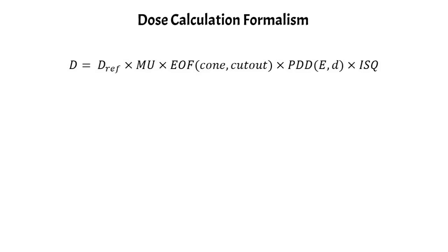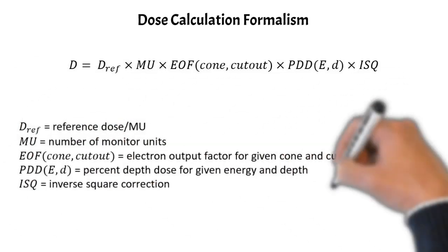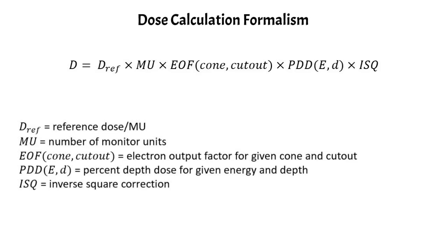This is the formalism here, and I'll write down a few of the terms. DREF is your reference dose per monitor unit established during your calibration. MU is number of monitor units. EOF is your electron output factor, which is a function of your cone size and also your cutout size. Then you have a percent depth dose, or PDD, which is a function of your beam energy and the depth of calculation. Then you have an inverse square correction as well.